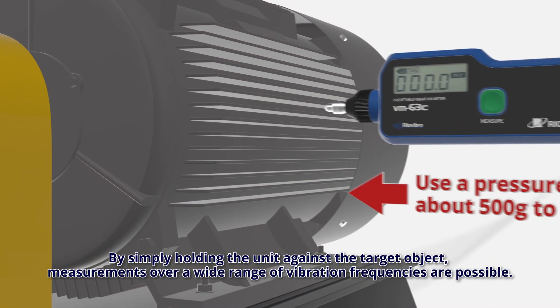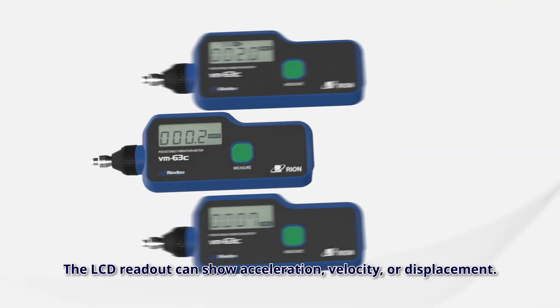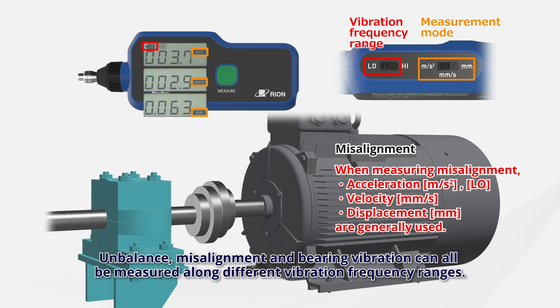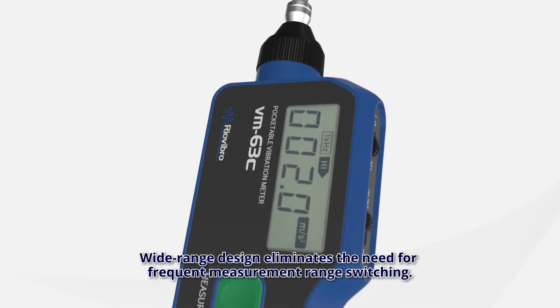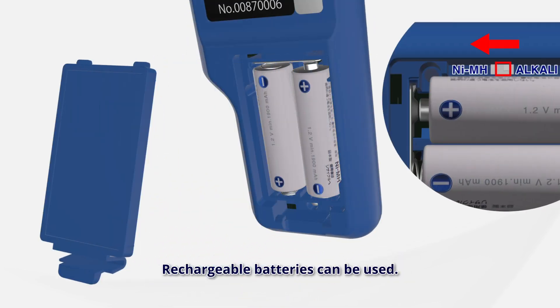By simply holding the unit against the target object, measurements over a wide range of vibration frequencies are possible. The LCD readout can show acceleration, velocity, or displacement. Unbalance, misalignment, and bearing vibration can all be measured along different vibration frequency ranges. The wide range design eliminates the need for frequency measurement range switching. Rechargeable batteries can be used.